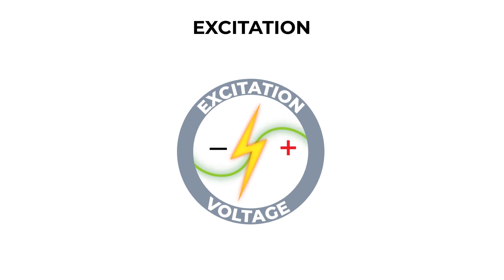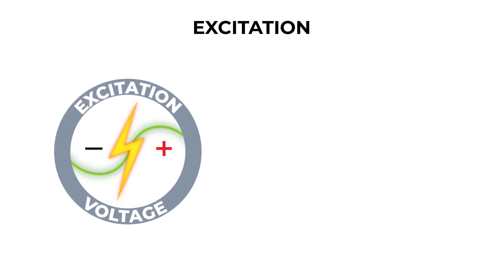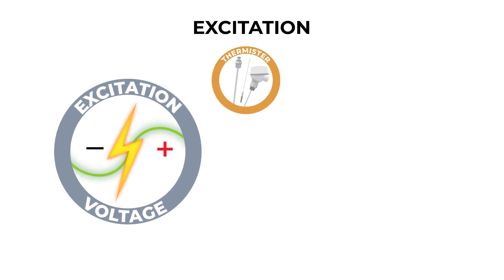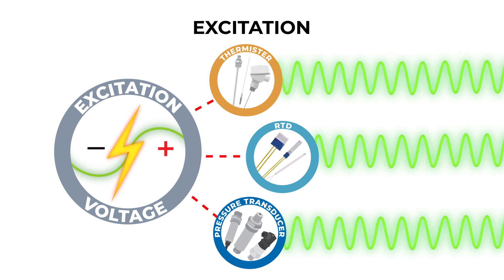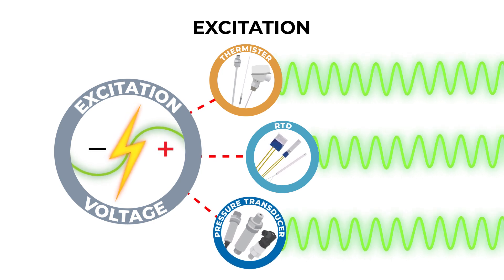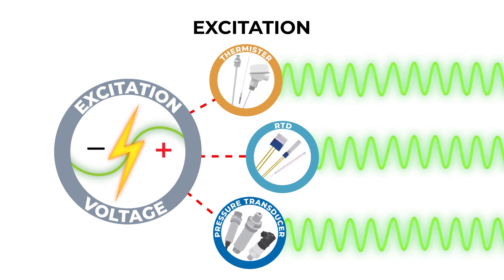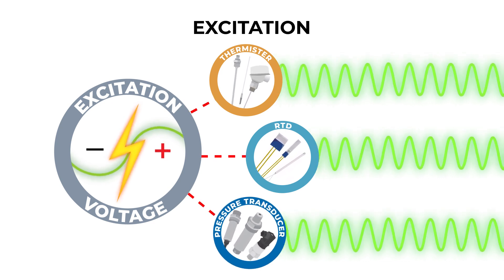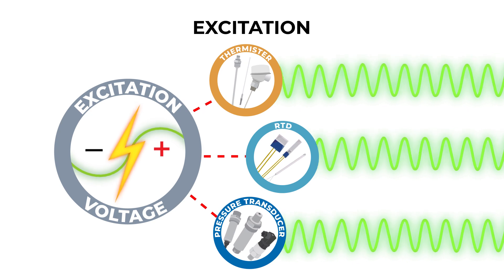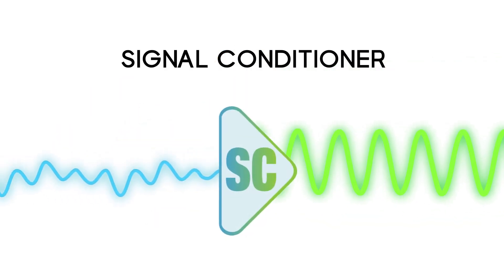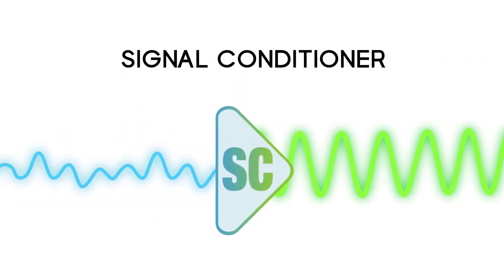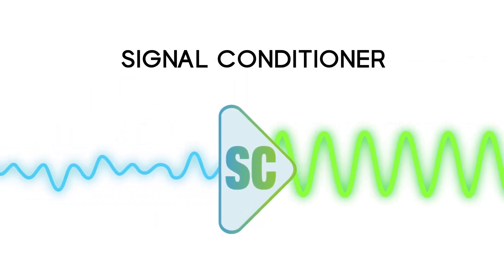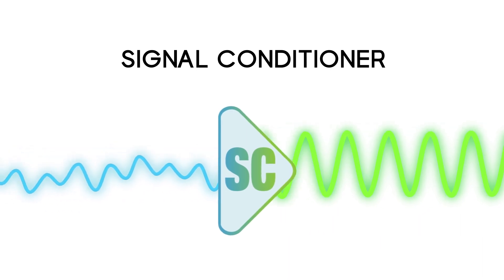Excitation voltage is required for the operation of an active sensor such as a thermistor, RTD, or a pressure sensor. The stability and accuracy of the excitation signal directly affects the stability and accuracy of the sensor. So when you're speccing out a process measurement system, be sure not to overlook the importance of signal conditioning.